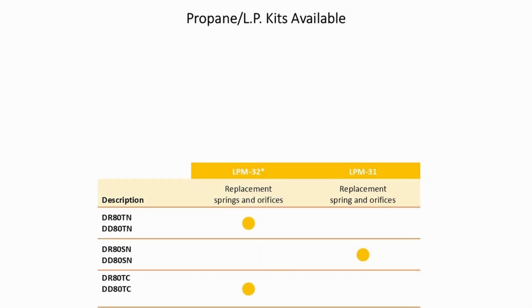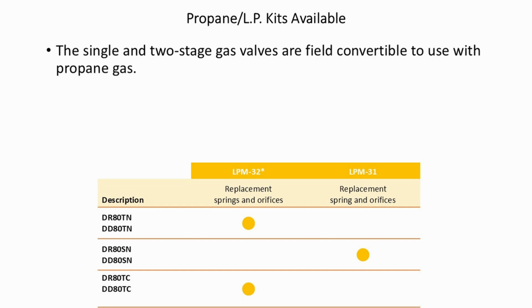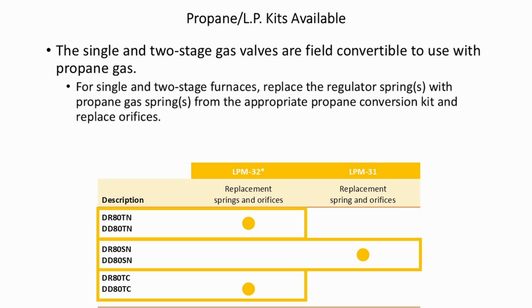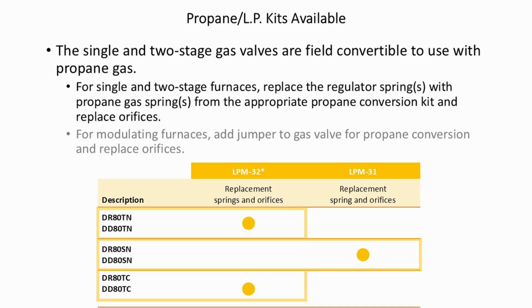Propane LP kits. The single and two-stage gas valves are field convertible to use with propane gas. For single and two-stage furnaces, replace the regulator spring or springs with propane gas spring or springs from the appropriate propane conversion kit and replace orifices. For modulating furnaces, add a jumper to the gas valve for propane conversion and replace the orifices.